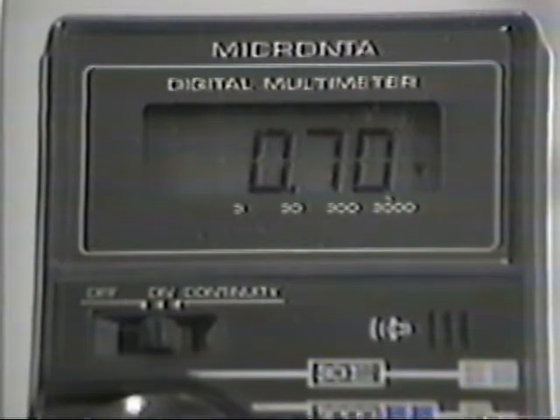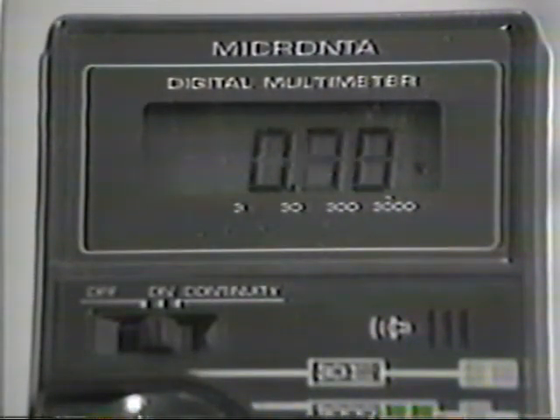As long as there is coolant covering the probe, the terminal 2 voltage will remain low, about 0.7 volts, as you see here, because the probe has a ground. If a coolant leak develops and the coolant drops away from the probe, the ground goes away and the terminal 2 voltage will climb, as shown by this digital meter. At 2.5 volts, the module triggers the low water alarm by grounding the light and bell through post 3 to post 4, which is the module ground connection. Think of the module as having a switch between terminals 3 and 4 that does this for us.